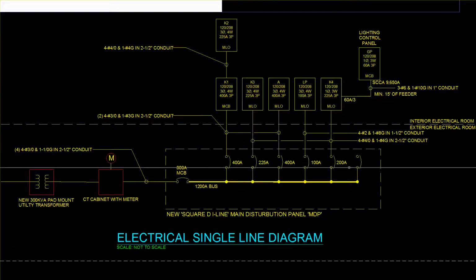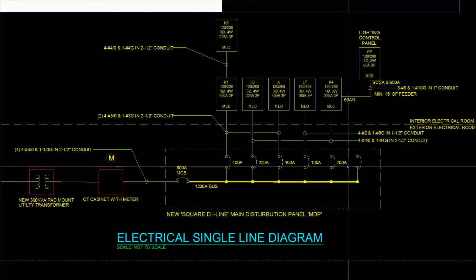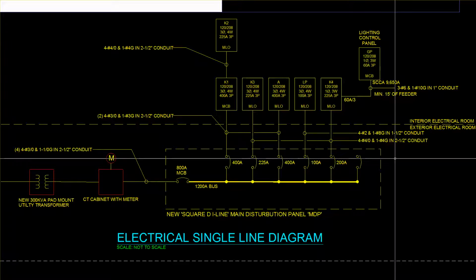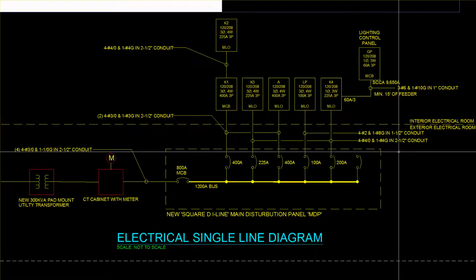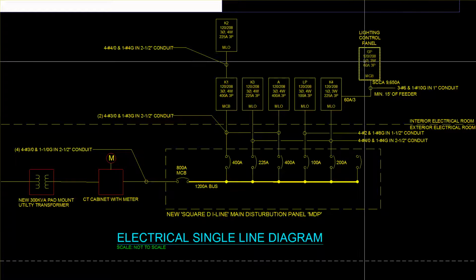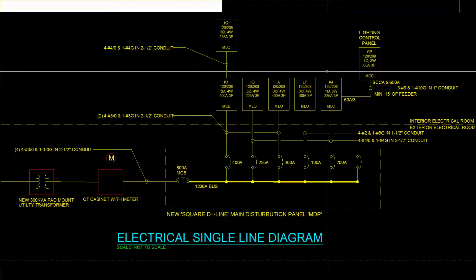And then K4, which is fed directly from the MDP. And you see it's fed with a slightly smaller circuit breaker. But we went ahead and ran the larger conductor to it because we have this particular lighting subpanel. And then we also know that they want to add more loads in the future to panel K4.